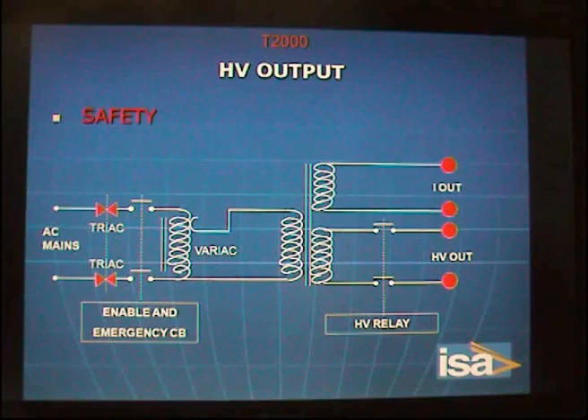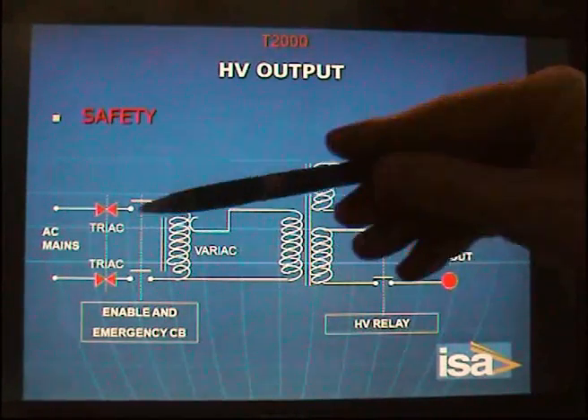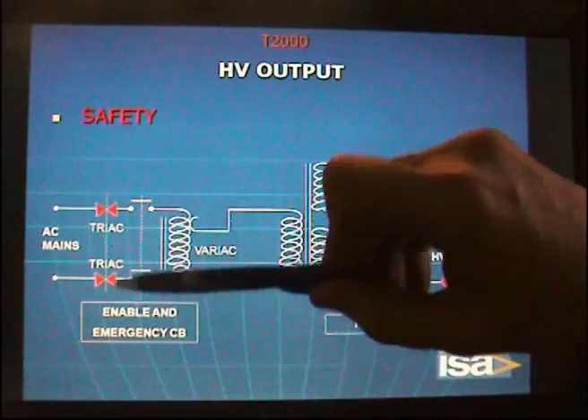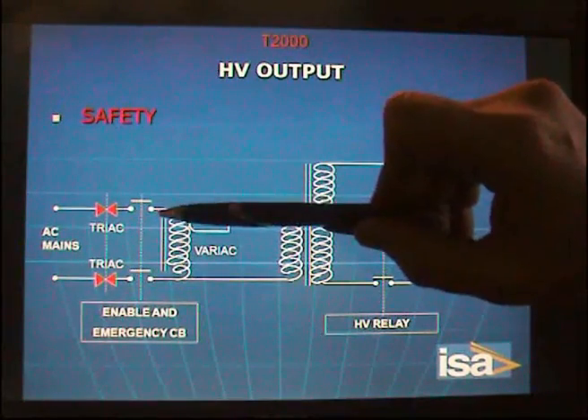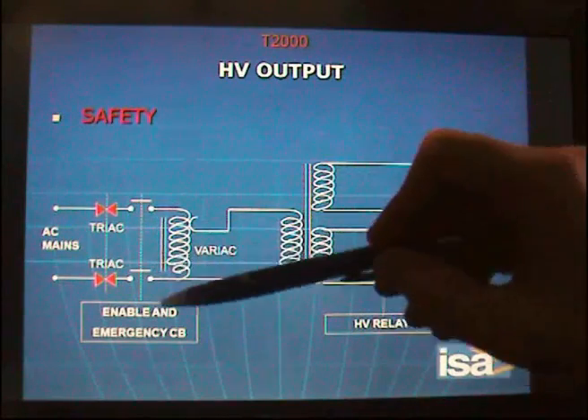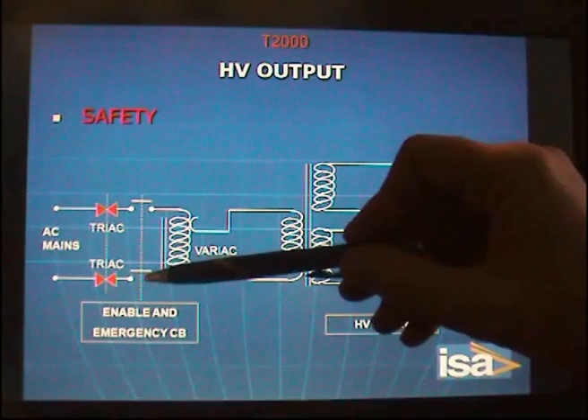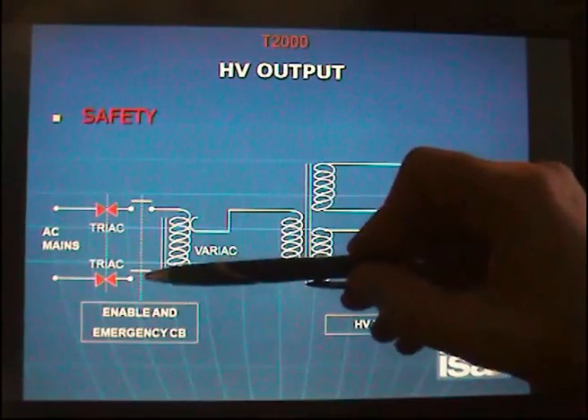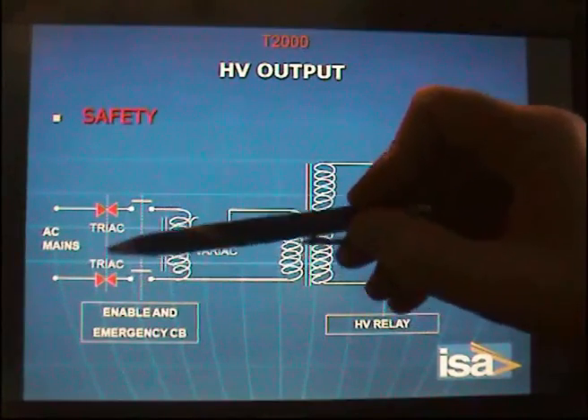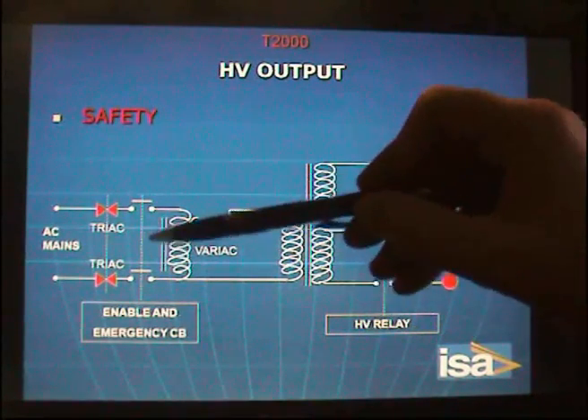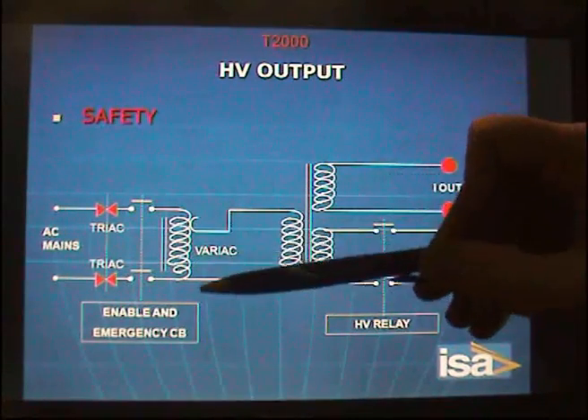Before continuing with this test that involves the generation of high voltage, I wish to tell you something about the safety that we have inside our test set. This is a very, very coarse schematic of the test set. Here the power supply is connected. We have a triac to open or close the circuit going to this variac. But the first thing that we have is an electromechanical circuit breaker. When you press the red emergency button in front of the test set, you open the circuit breaker regardless of anything that the microprocessor is doing. So there is no possibility of this safety being not operational if there is a microprocessor jam.